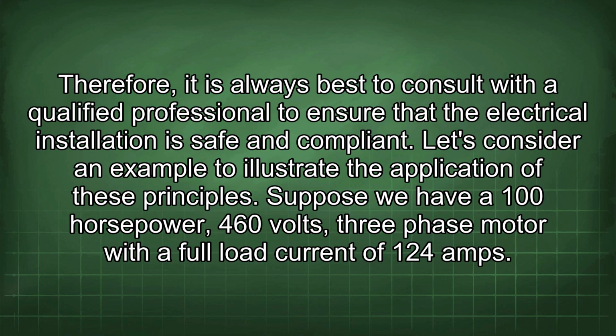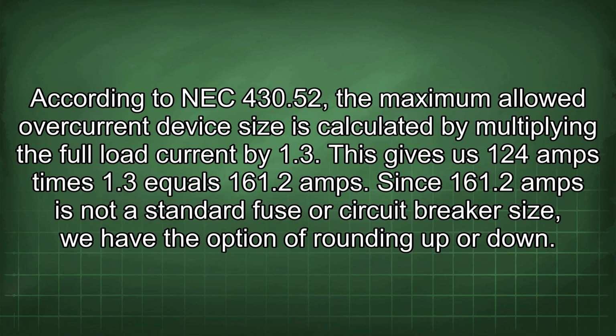Suppose we have a 100 horsepower, 460 volts, three-phase motor with a full load current of 124 amps. According to NEC 430.52, a maximum allowed overcurrent device size is calculated by multiplying the full load current by 1.3. This gives us 124 amps times 1.3 equals 161.2 amps.